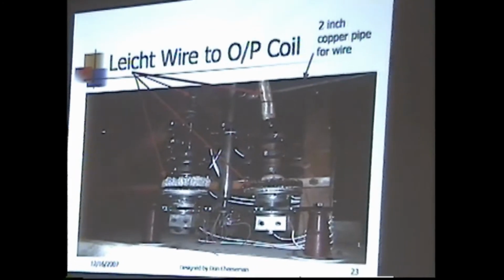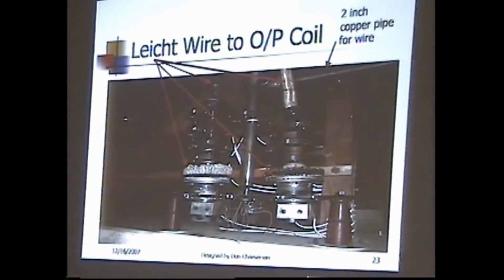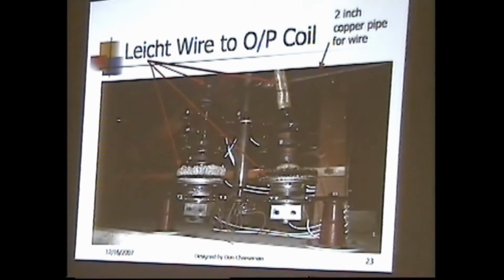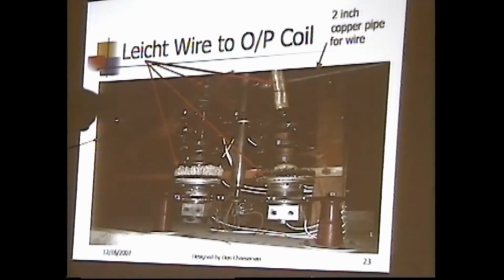And these were on... This is interesting. The Leicht wire went down here on copper pipe. The copper pipe was carrying continuously 700 amps. That pipe isn't a water pipe, it's the final output from the amplifiers, and then terminated 6,000 36-gauge copper wires, all varnished and silk insulated, going up through those current transformers, and that was the output from the coil.